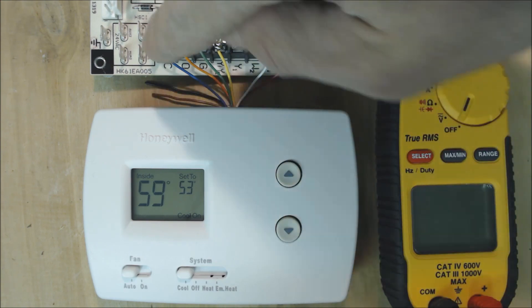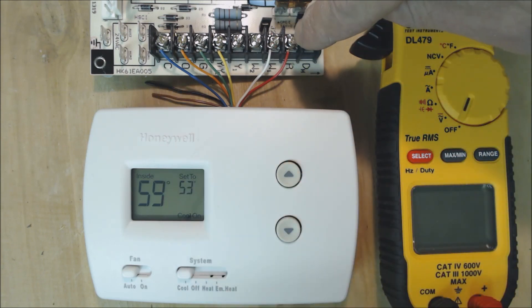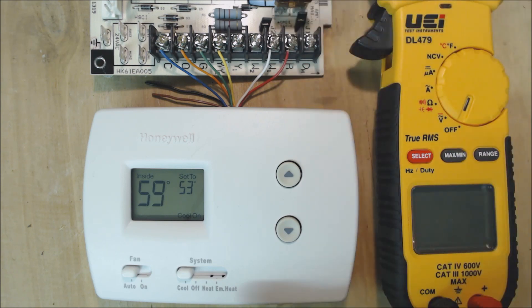It doesn't need the C wire to power the thermostat if you have batteries. However, you do need this R 24 volt power wire coming into the thermostat. W right here is for heat—that would be your emergency heat or auxiliary heat.